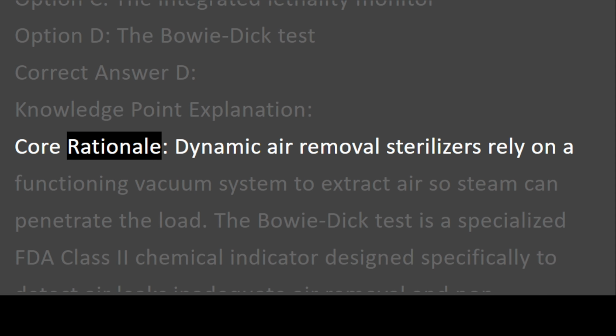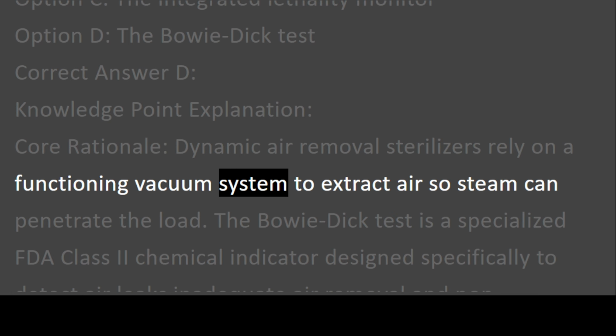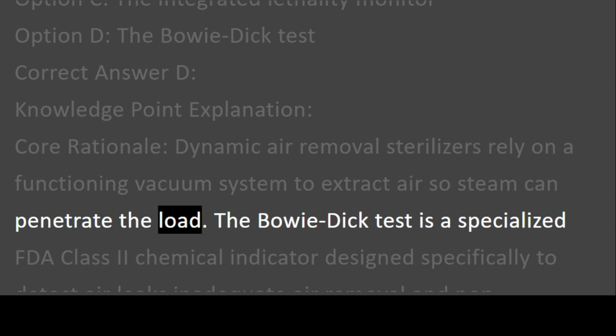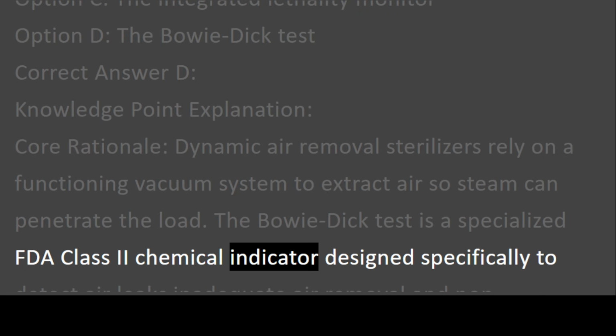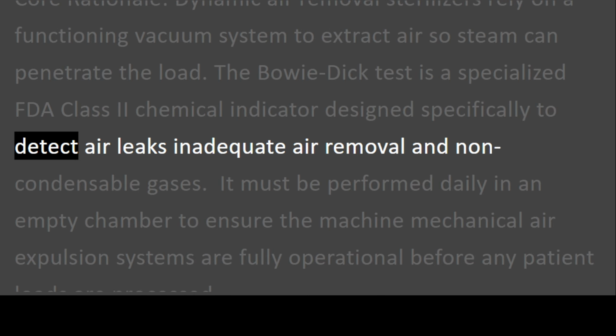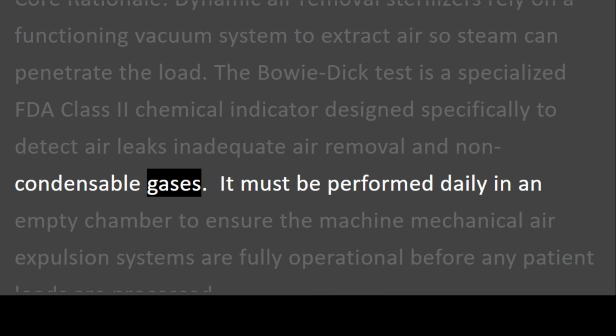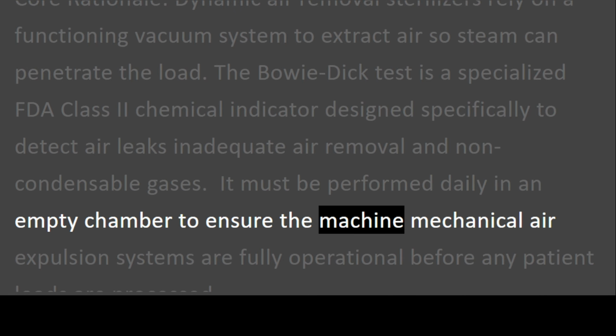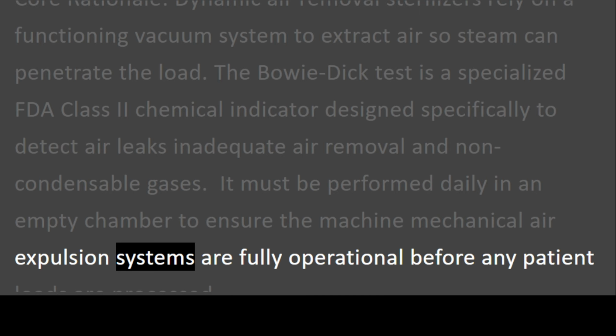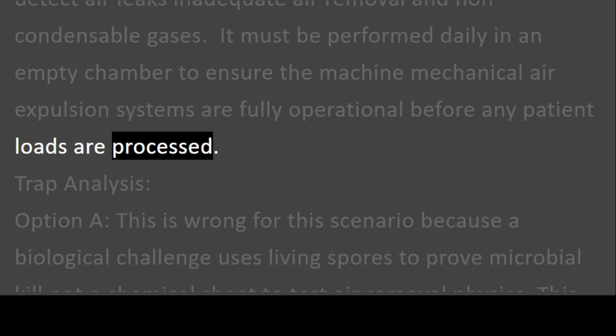Core rationale. Dynamic air removal sterilizers rely on a functioning vacuum system to extract air so steam can penetrate the load. The Bowie-Dick test is a specialized FDA Class 2 chemical indicator designed specifically to detect air leaks, inadequate air removal, and non-condensable gases. It must be performed daily in an empty chamber to ensure the machine's mechanical air expulsion systems are fully operational before any patient loads are processed.